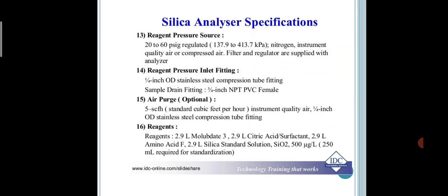Reagent pressure inlet fitting: 1/4-inch OD stainless steel compression tube fitting. Sample drain fitting: 3/4 inch NPT PVC female. Air purge: 5 SCFH, standard cubic feet per hour. SCFH means standard cubic feet per hour. The instrument quality air uses a 1/4-inch OD stainless steel compression tube fitting.